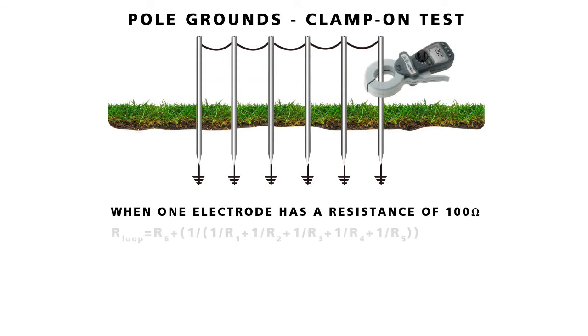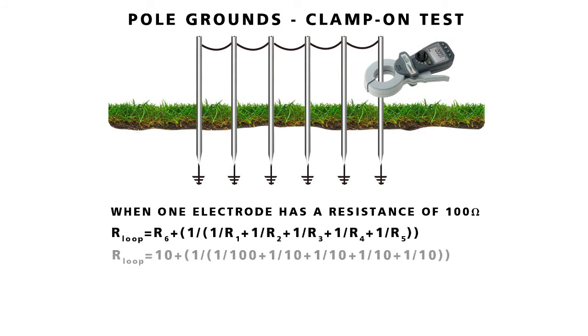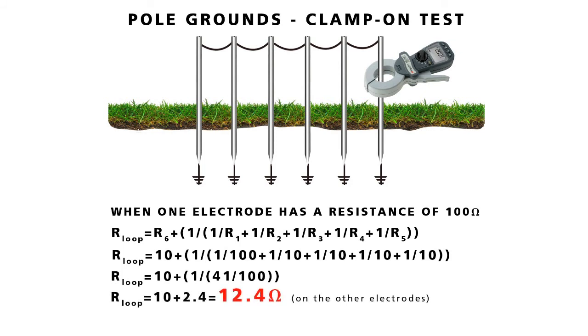But what if the high resistance ground was part of the parallel return? The calculation shows that it makes only a negligible contribution to the measurement. In a parallel system, a bad ground does not have a large effect.